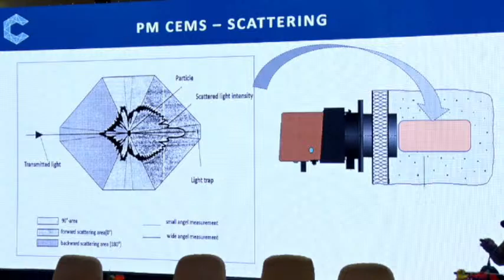Forward scatter, as I said, has better sensitivity and is suitable for low and medium concentration. This low and medium is for Indian conditions. It is not low and medium for Europe, because there it is 5 milligram, 2 milligram, we cannot even think about that. So we are talking 20, 30 like this. A small scattered light intensity requires high measurement accuracy. That's what we discussed. It occurs at a small angle to the incident light, so proper shielding of the receiver from direct sunlight is crucial.